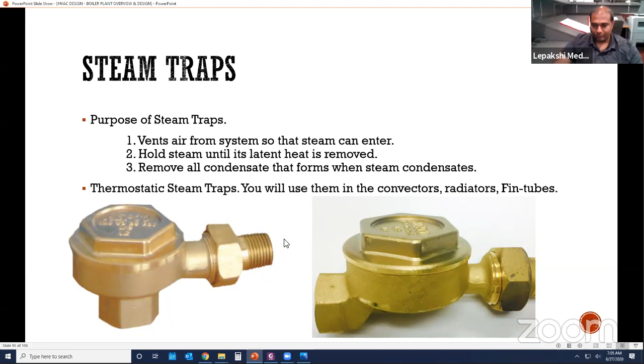Again, there are two types of traps. One is thermostatic traps, which you can see over here. This is an angled trap, which means the supply is coming from the bottom and this is tied onto the radiator or convector, fin tube, whatever you call it. And this is a straight trap, which means it's inline. And you have the float and thermostatic trap, simply called the F&T trap, which is a float and thermostatic steam trap.